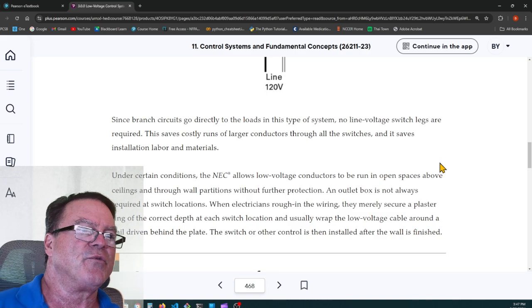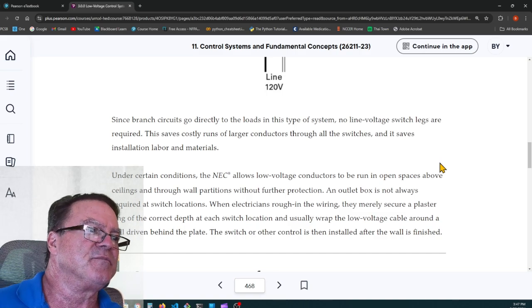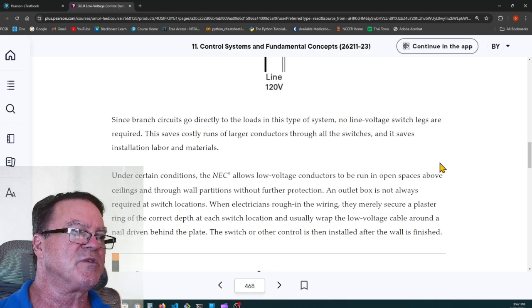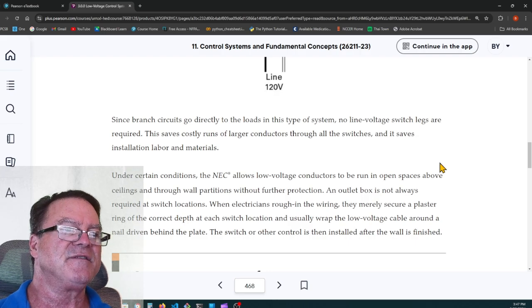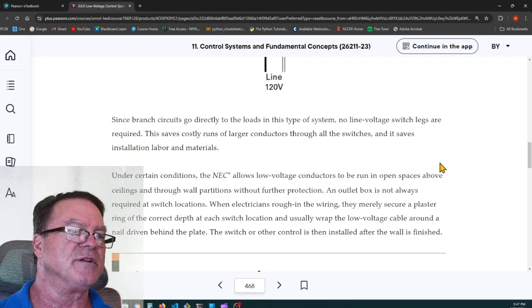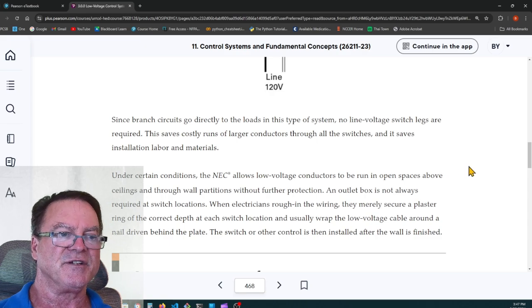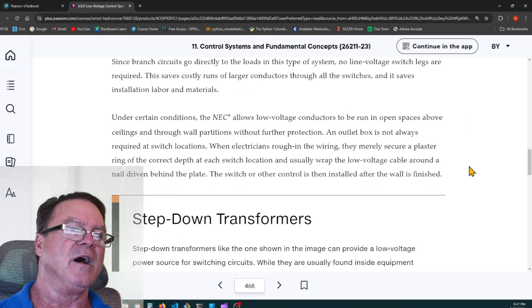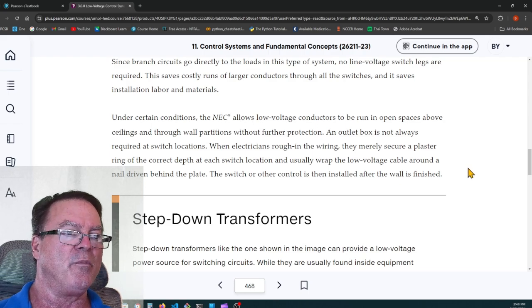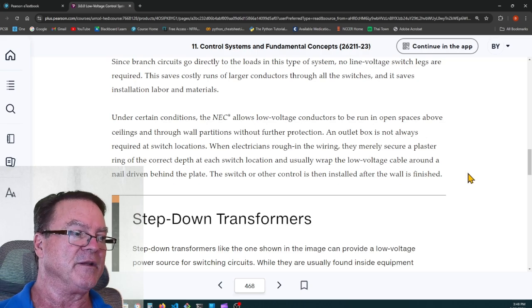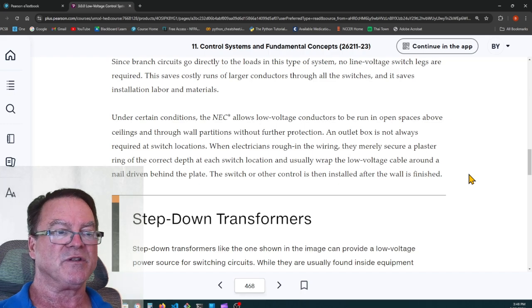Since branch circuits go directly to the load in this type of system, no line voltage switch legs are required. This saves costly runs of larger conductors through all the switches, and it saves installation labor and materials. Under certain conditions, the NEC allows low voltage conductors to be run in open spaces above ceilings and through wall partitions without further protection. An outlet box is not always required at switch locations.